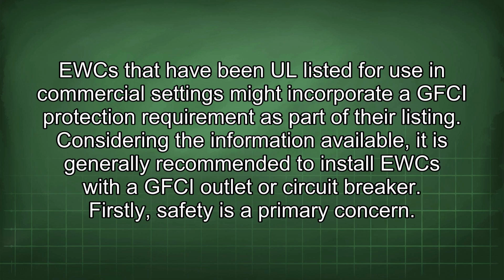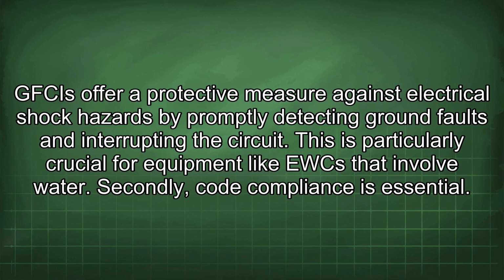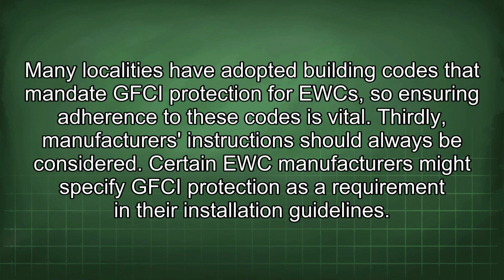Firstly, safety is a primary concern. GFCIs offer a protective measure against electrical shock hazards by promptly detecting ground faults and interrupting the circuit. This is particularly crucial for equipment like EWCs that involve water. Secondly, code compliance is essential. Many localities have adopted building codes that mandate GFCI protection for EWCs, so ensuring adherence to these codes is vital. Thirdly, manufacturers' instructions should always be considered. Certain EWC manufacturers might specify GFCI protection as a requirement in their installation guidelines.